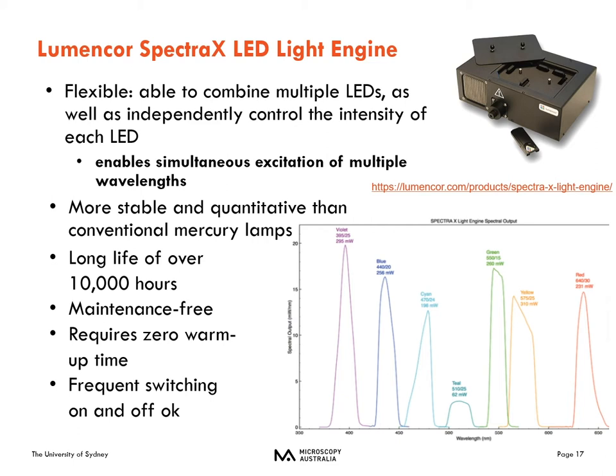We also have systems that use the Lumencor Spectra X LED light engine. What's neat about the Spectra X is that instead of being a white light source, it provides individual wavelengths of light. You can turn off individual wavelengths without using excitation filters — it all comes right from the light source. This enables simultaneous excitation of multiple wavelengths without a filter wheel, which can be really useful for experiments with two cameras.